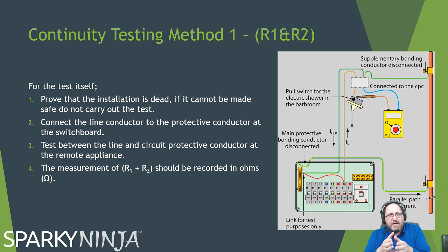So here they've disconnected the bonding to free up the earth on the bar. I would say disconnect the earth from the bar. That's what I'd do. Alright, take the circuit's line, take the circuit's earth, put them together, either in the breaker or in a connector, or I use the Wago flex lever things. They're together, okay? Then go to the final point of the circuit and measure between them. Now if you have continuity of your protective conductor, then you'll get a reading. If it's broken anywhere, you'll get no reading. And that's it. That's method 1.